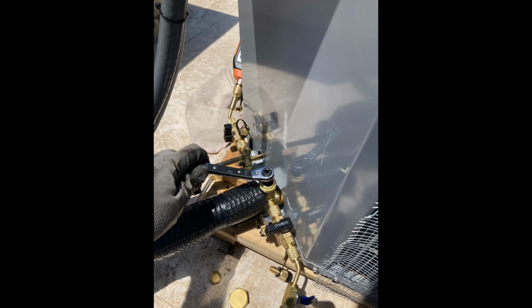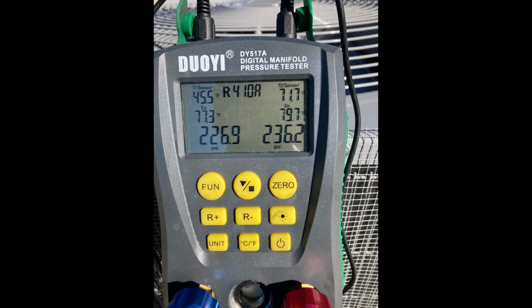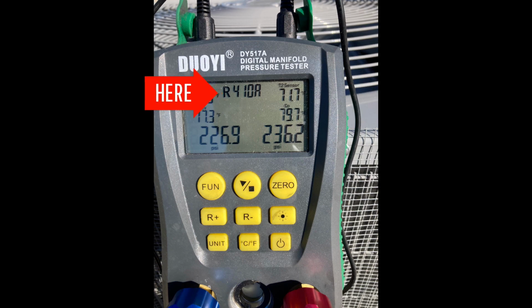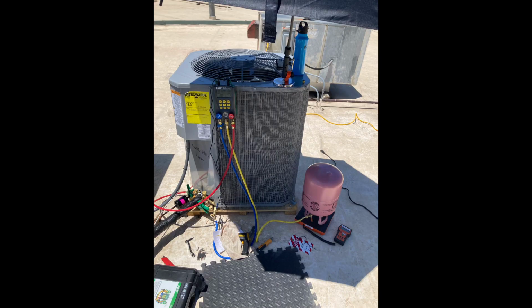Once we do that, we'll turn on power to the condenser. The air handler is running downstairs. The condenser is running on the roof. We'll hook up our manifold gauge set here and check for temperature and pressures. Again, this is a R410A system. Because it's a longer line set, I'm going to need to add a tiny bit of refrigerant to make up for that long line set. And we'll use a PT chart, a pressure temperature chart, to make sure we get the charge just right. And that'll complete this project.